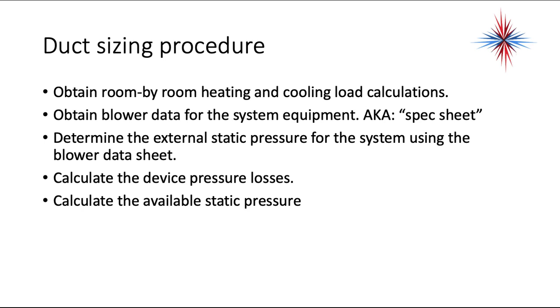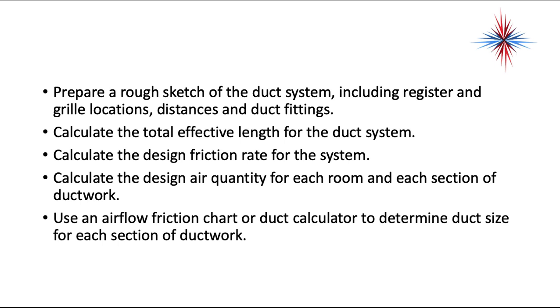To do duct sizing properly, you must obtain room-by-room heating and cooling load calculations, obtain the blower data for the system equipment (also known as a spec sheet), and determine the external static pressures using the blower data sheet. You need to calculate the device pressure losses and the available static pressure. Then prepare a rough sketch of the duct system including register and grill locations, distances, and duct fittings. Calculate the total effective length, the design friction rate, and the design air quantity for each room and each duct section. Then use an airflow friction chart or duct calculator to determine duct size for each section.